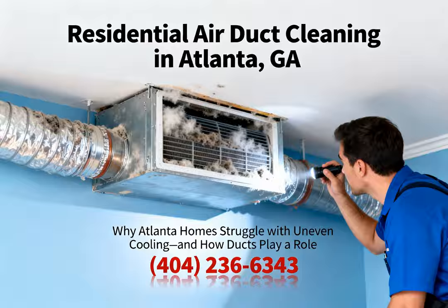Your lungs might have the capacity, but the physical resistance of the blanket is too high. You just suffocate. That's a great visual. Right. So if I pull out my flimsy paper filter and jam a thick 5-inch medical-grade MERV 16 filter into my air conditioner, won't the physical resistance suffocate the blower motor? Won't that just recreate the exact airflow restriction we just fixed?